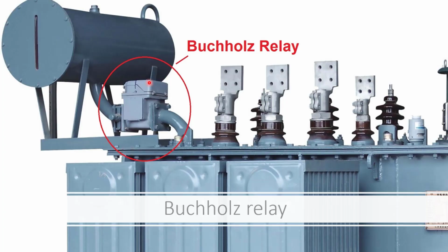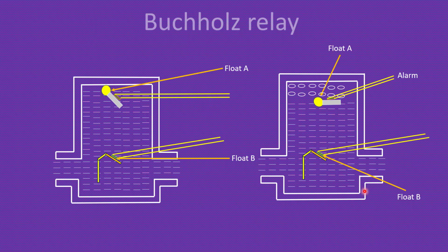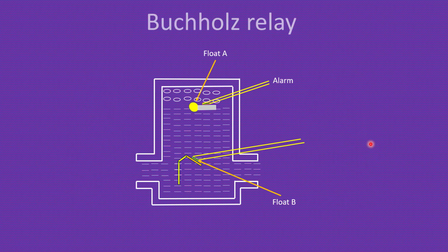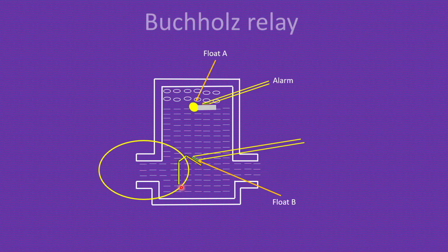If you look at this closely, you can see a valve-like arrangement on top, right? When we open this, the gas will be released. A trained person can understand the fault nature by inspecting the gases. There is one more float, right? Float B. What is its function? This float B will not be activated in normal conditions, okay? Even if it's a minor fault, it will not be activated. When the transformer is in normal condition, the oil is passing to the conservator through the Buchholz relay and it is hitting float B. There will not be any effect in the normal condition.